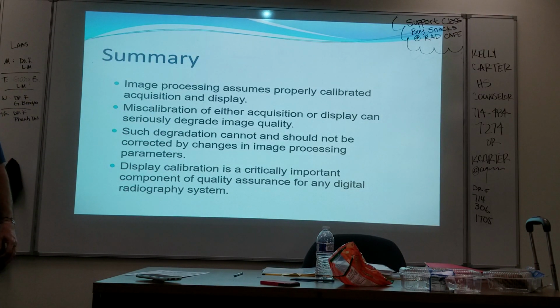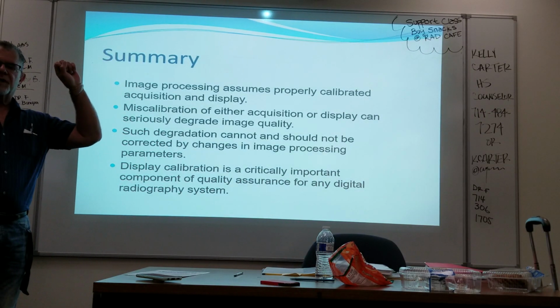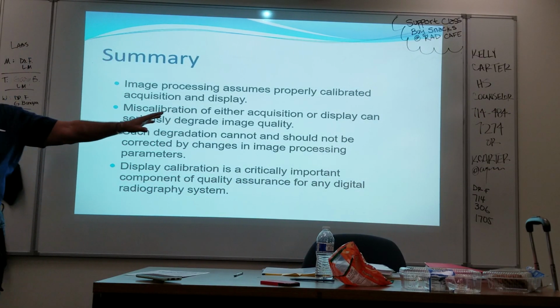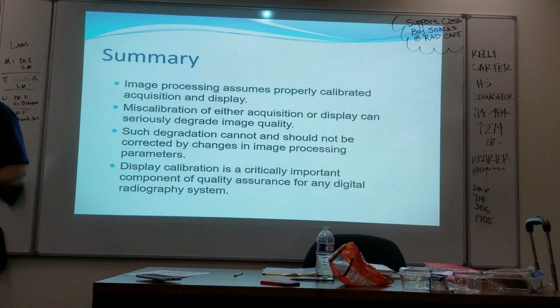It was because they were manipulating this and not the system. And so it's really important that your system is calibrated. So what you see on the screen and what comes out of the printer or what comes up on the physician workstation looks the same. Okay. Display calibration is a critically important component of quality assurance for any digital radiography or fluoroscopy system.